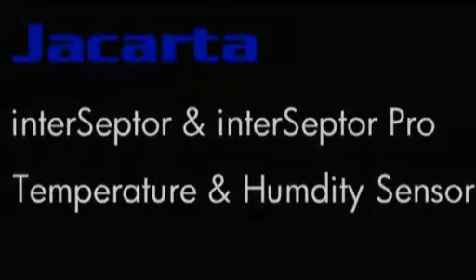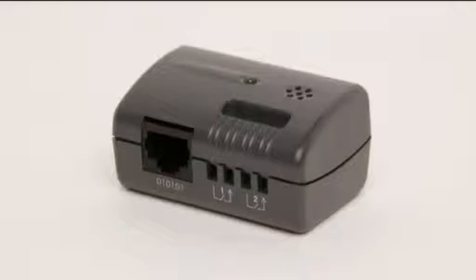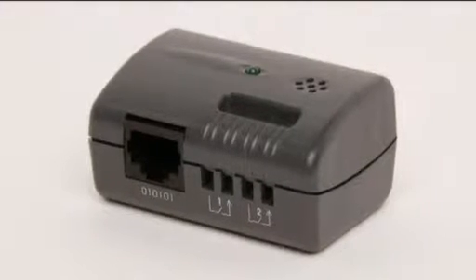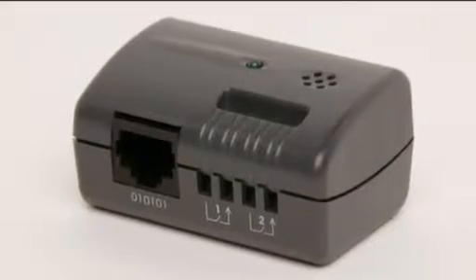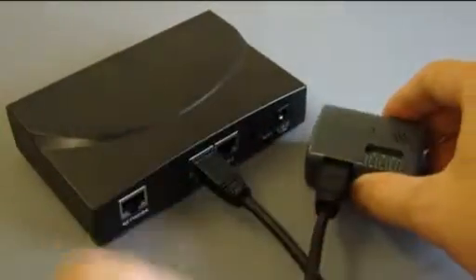The Jacarta interSeptor temperature and humidity sensor is supplied as standard with all Jacarta interSeptor and interSeptor Pro monitoring devices. The sensor is small and unobtrusive and connects to the interSeptor using standard CAT5 cable up to 80 meters in length.